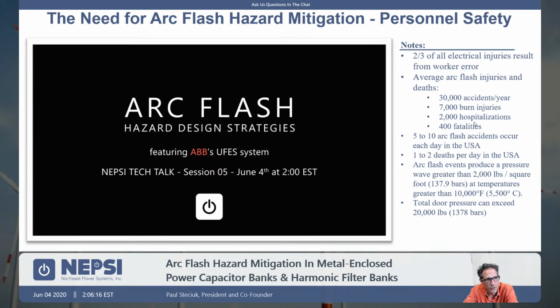Each year, there are 400 fatalities in the United States related to arc flash. There's 5 to 10 arc flash accidents per day in the United States, and this is significant. When an arc flash event occurs, there's an arc through air within the enclosure, in our case within the metal enclosed capacitor bank or harmonic filter bank. That arc flash results in a significant temperature and pressure buildup within the enclosure. It can be on the order of 2,000 pounds per square foot. If you think about the square area of a door, that's over 20,000 pounds on a door itself. So under an extreme arc flash condition, it is no doubt going to cause damage within the equipment.